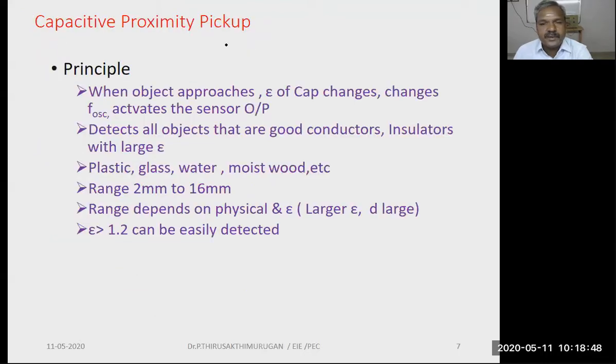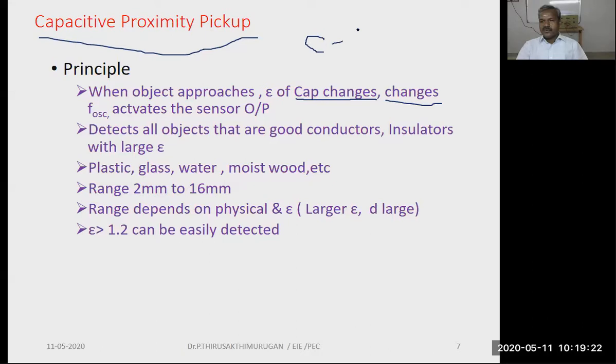Next is the capacitive proximity pickup. So when an object approaches, the dielectric constant of the capacitance changes. So the change in the dielectric capacitance increases the oscillator frequency, which activates the sensor output. Okay, so this is the capacitive proximity pickup. You know why I am talking about the dielectric? With the help of the basic formula, C equals epsilon A by D. So here, by maintaining A and D constant, we are detecting only the variation of the dielectric constant of the material, the object which is approaching the sensor head.